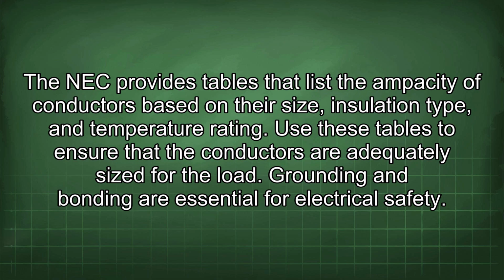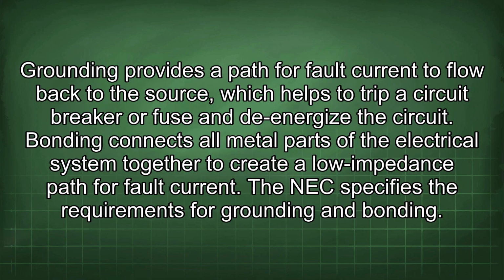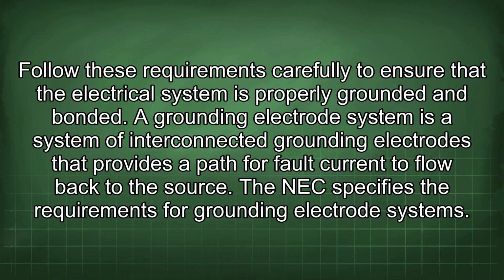Grounding and bonding are essential for electrical safety. Grounding provides a path for fault current to flow back to the source, which helps to trip a circuit breaker or fuse and to de-energize the circuit. Bonding connects all metal parts of the electrical system together to create a low impedance path for fault current. The NEC specifies the requirements for grounding and bonding. Follow these requirements carefully to ensure that the electrical system is properly grounded and bonded.